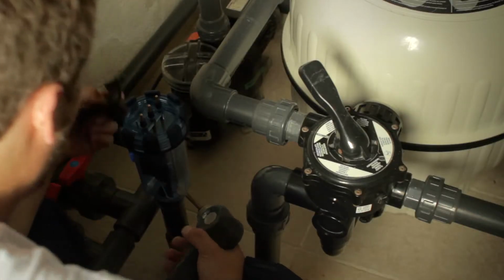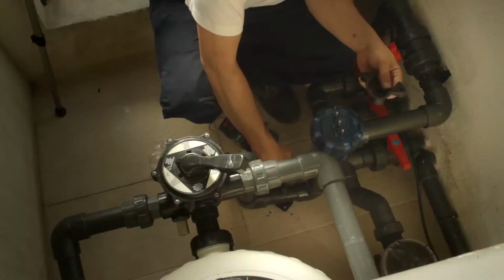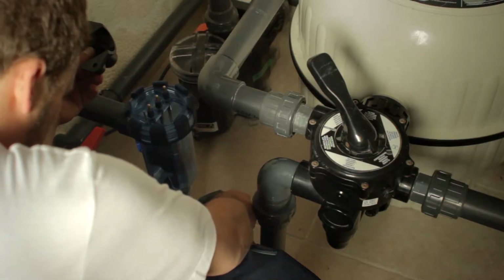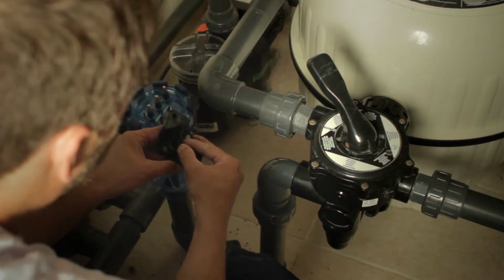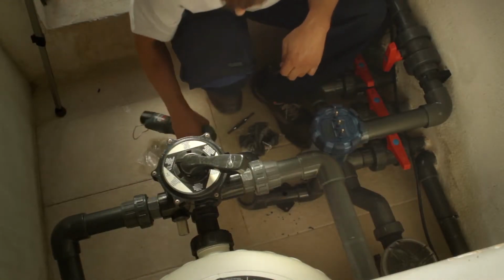Make a hole in the pipe. The diameter of the hole should be less than the seal. This ring will be for the measuring probe. We will install another one after the cell for acid injection. Here you can use an 18mm drill bit.